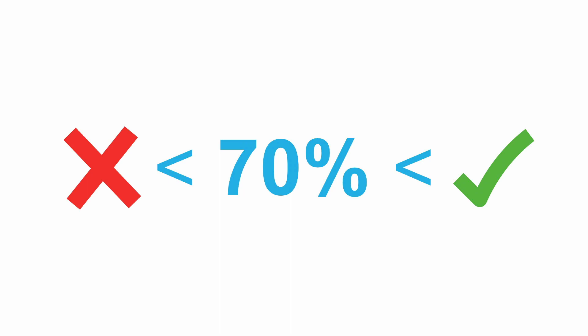The way it works is quite simple. In comparing the two templates, if they resemble each other by greater than 70%, then this is considered a normal rhythm or a supraventricular tachycardia. For that reason, therapy is withheld. Alternatively, if the rhythms are not 70% similar in their template, then therapy is delivered as a ventricular event is assumed.